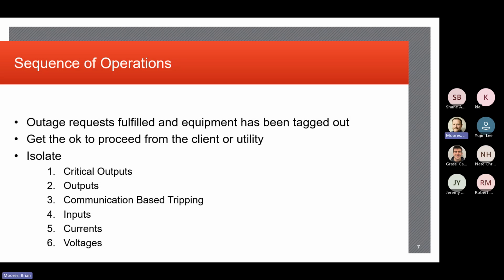So it's best to leave that for last. Generally, the order of operation would be critical outputs. That would be tripping breakers, the breaker fail initiate, anything that trips a lockout, right? And then your other outputs, because again, the relay is making decisions based on currents, voltages, and inputs. All of those things drive the logic to those outputs.